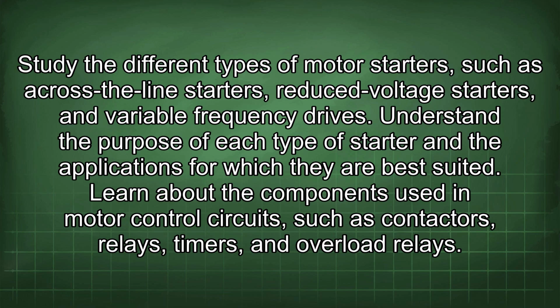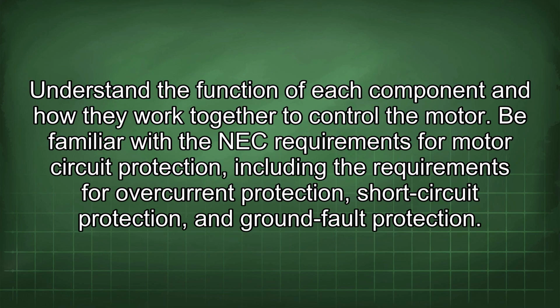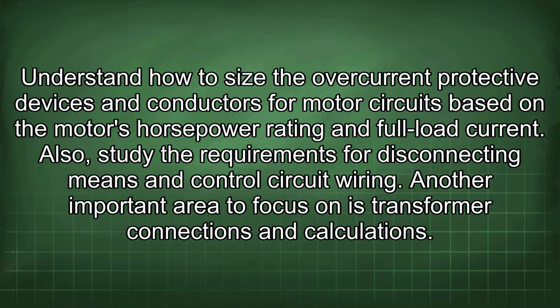Learn about the components used in motor control circuits, such as contactors, relays, timers, and overload relays. Understand the function of each component and how they work together to control the motor. Be familiar with the NEC requirements for motor circuit protection, including overcurrent protection, short circuit protection, and ground fault protection. Understand how to size the overcurrent protective devices and conductors for motor circuits based on the motor's horsepower rating and full load current. Also, study the requirements for disconnecting means and control circuit wiring.